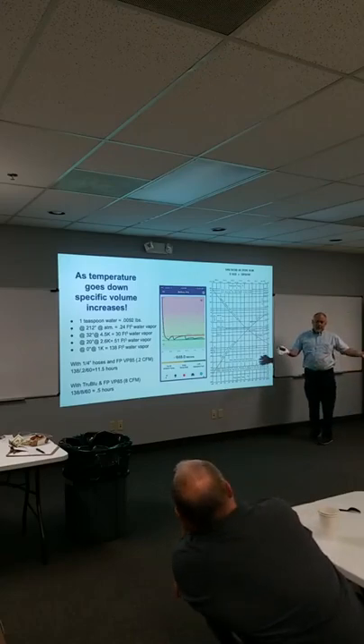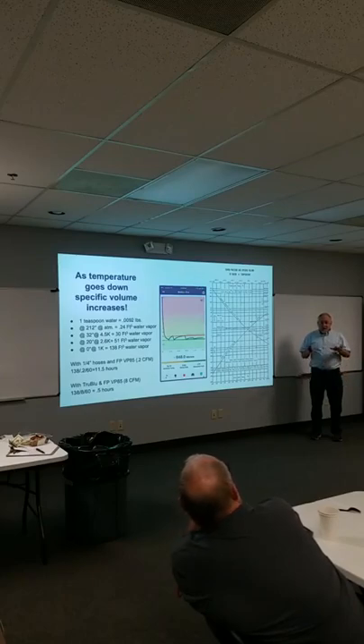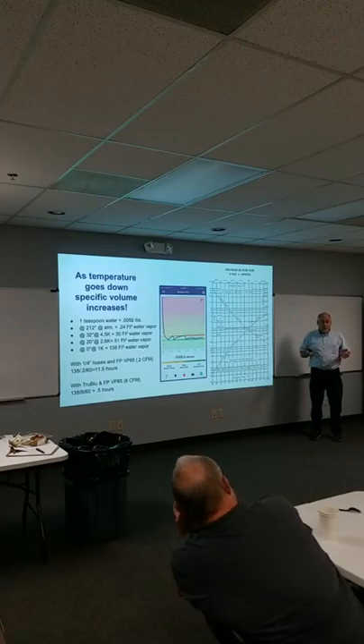Because you go, oh, the volume of the system is pretty darn small. It's not that big of a deal, right? There's not that much gas to remove. If you were to do the math and calculate the inside diameters of your tubings, you only have a cubic foot or two, maybe 3 or 4 cubic feet in a 5-ton system, the total volume, right? You go, well, 5 cubic feet, 5 CFM pump, 1 minute, should be down, right? It doesn't work that way, right?